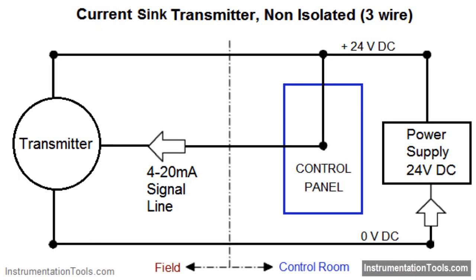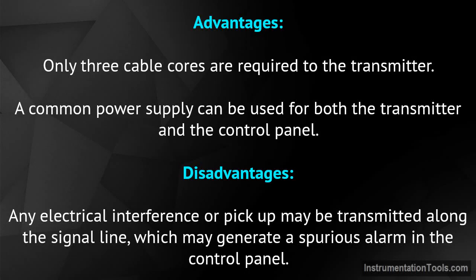Three-wire current sink transmitter non-isolated. The transmitter and control panel can use the same 0 volts and 24 volts DC supply lines. The 4 to 20 milliamp signal flows through the 0 volts DC line and the signal line to the controller. Advantages: only three cable cores are required to the transmitter.